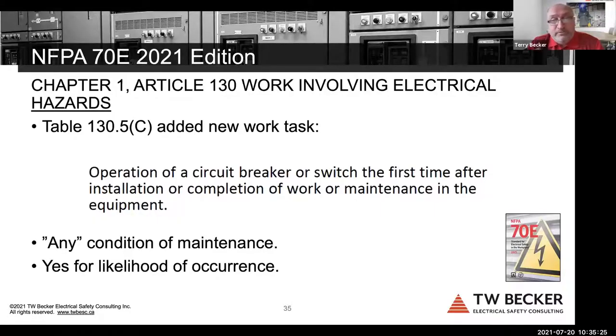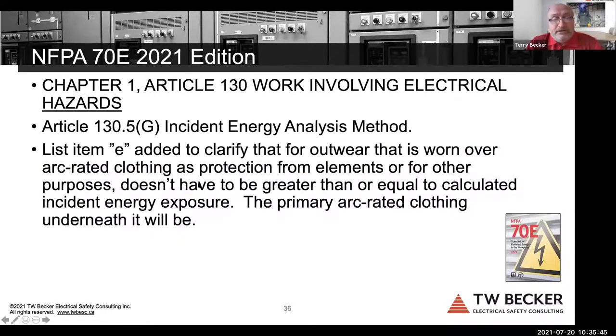Huge controversy, probably not going to go away, but this work task is independent of the other work task that says operating a circuit breaker, disconnect switch, contactor, or motor starter, which allows you, again, to make the decision based on normal or abnormal conditions, which is, in my opinion, how this should be managed for normal operation of electrical equipment.